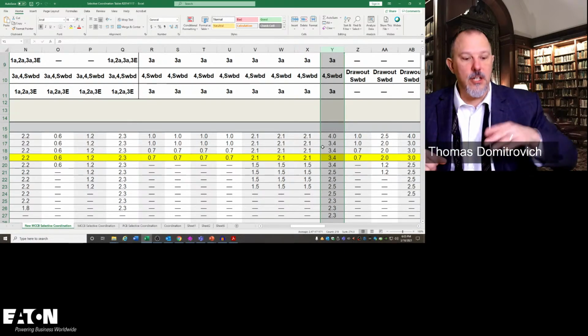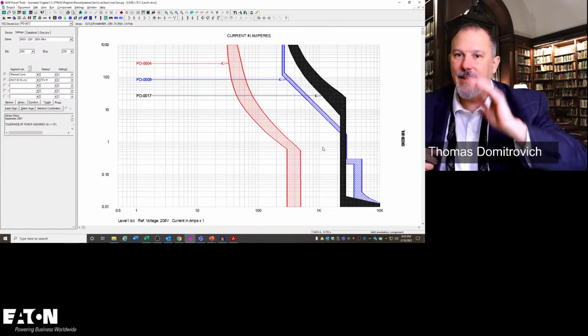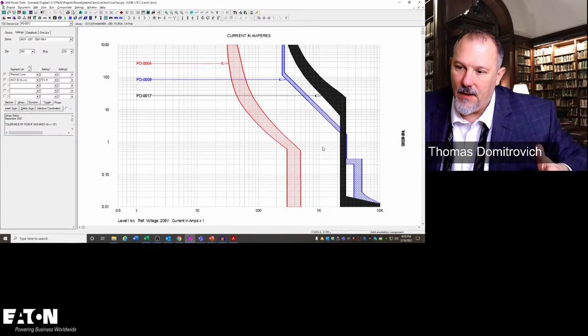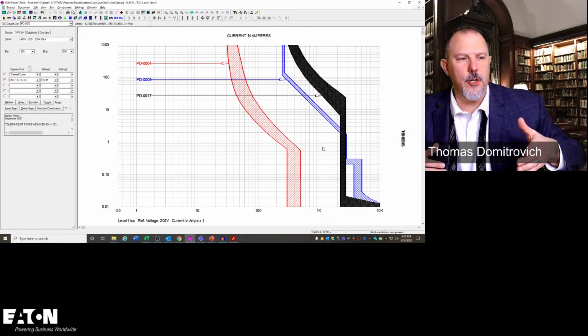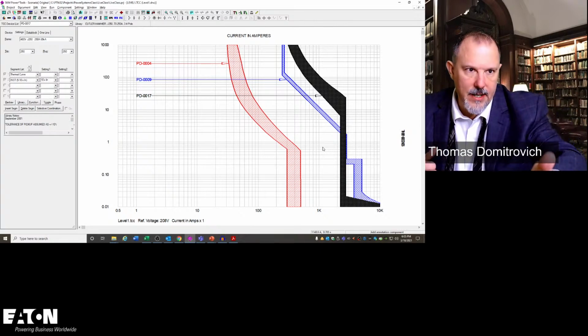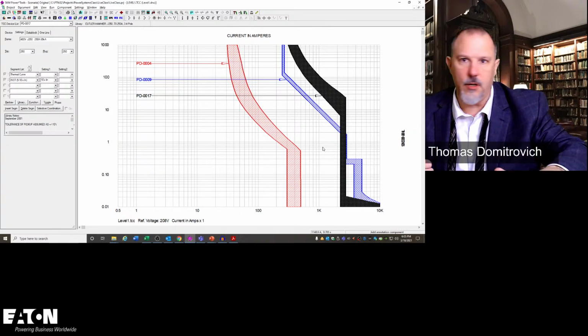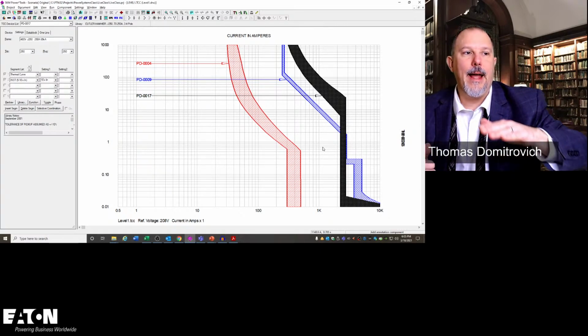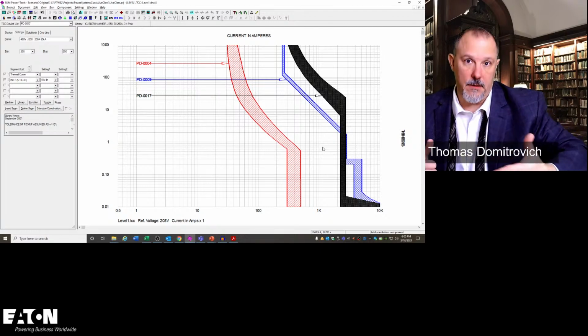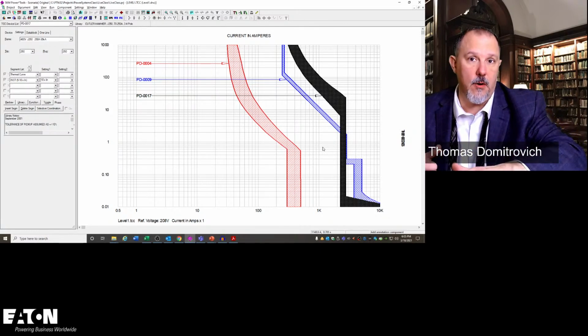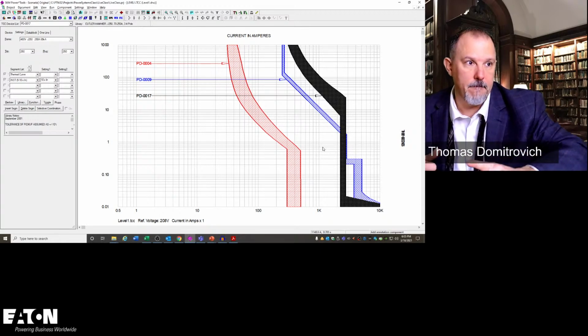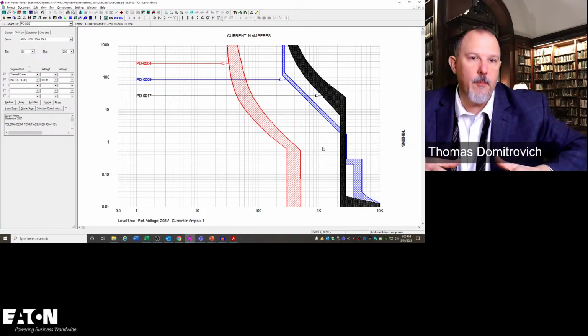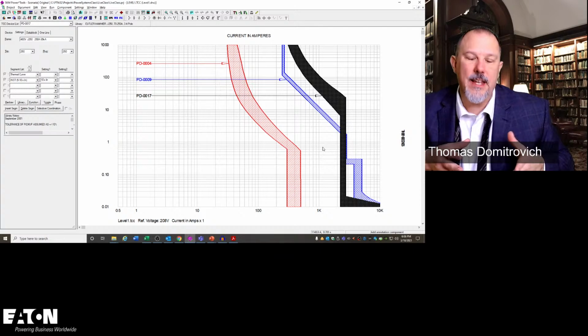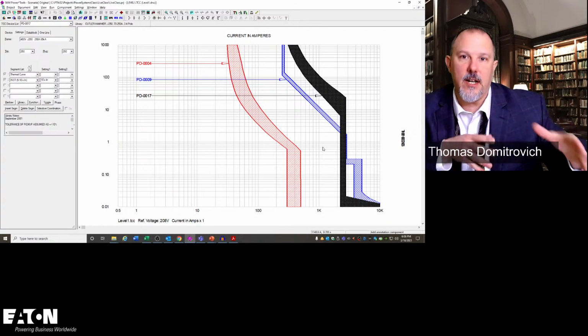Now, let's look at this, and this is how I go down the road of some people who will say 0.1 seconds does not consider any fault current value. And here's why I think that scares me. Now, remember, that's just a minimum requirement. We should be going above and beyond that bare minimum. And here's why. If I'm looking at a healthcare system, I'm looking at a hospital, a life safety system in a hospital, a critical system in a hospital.